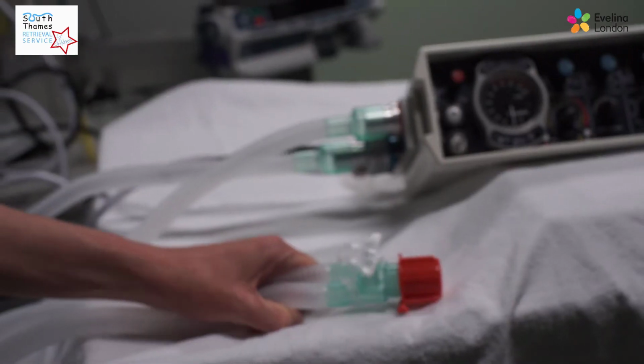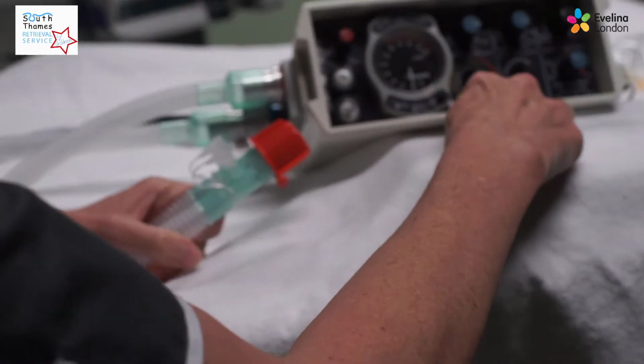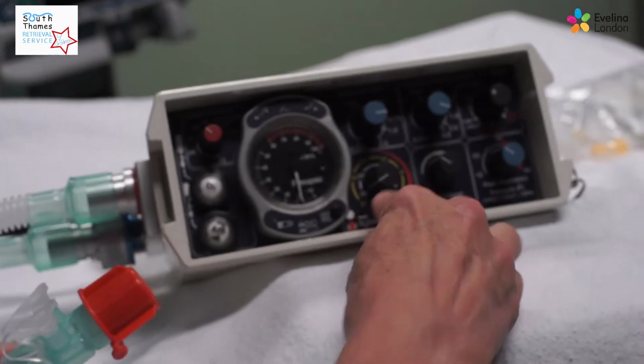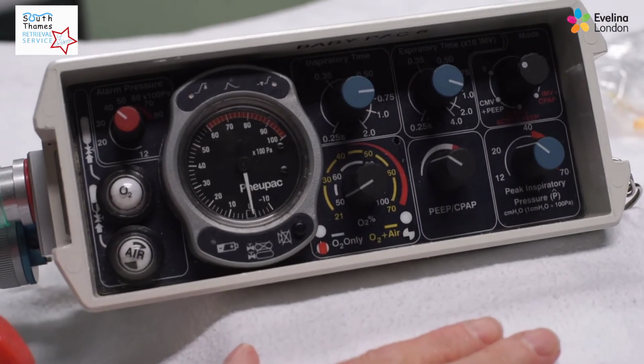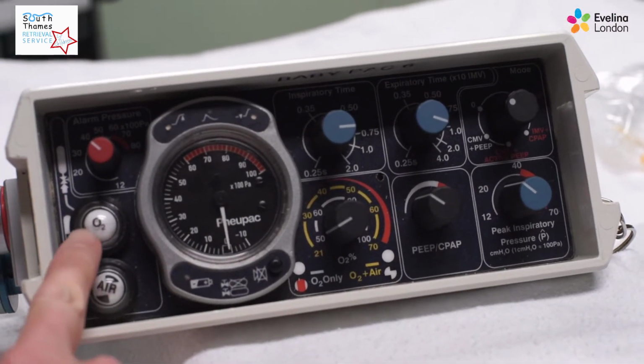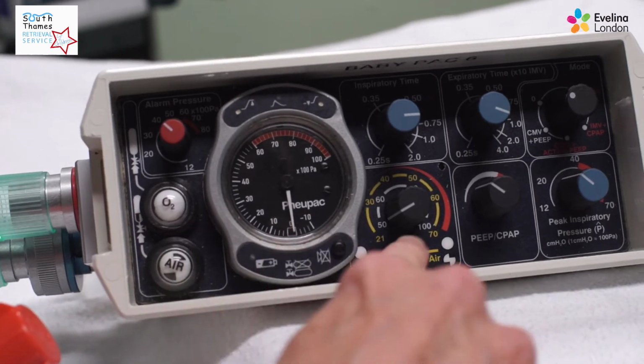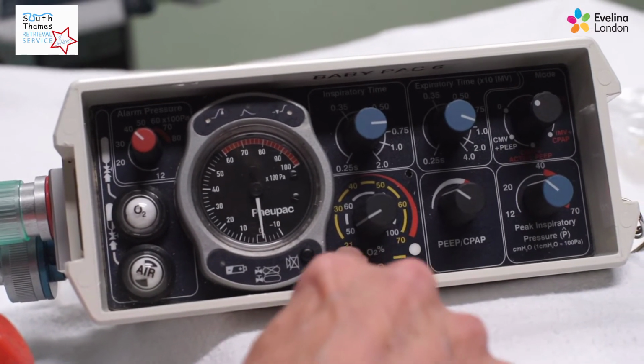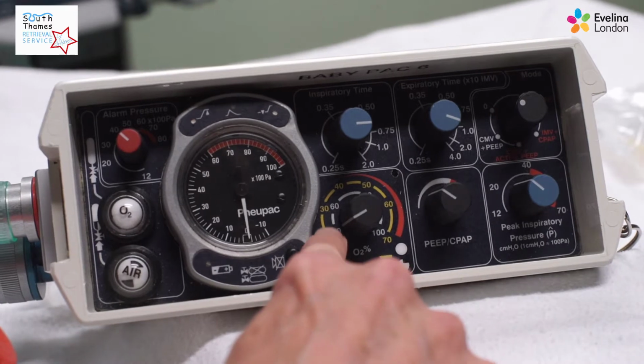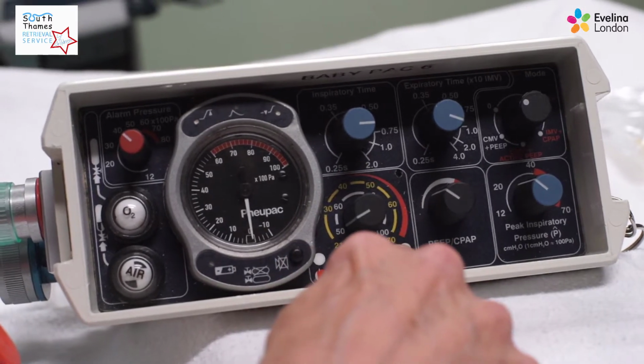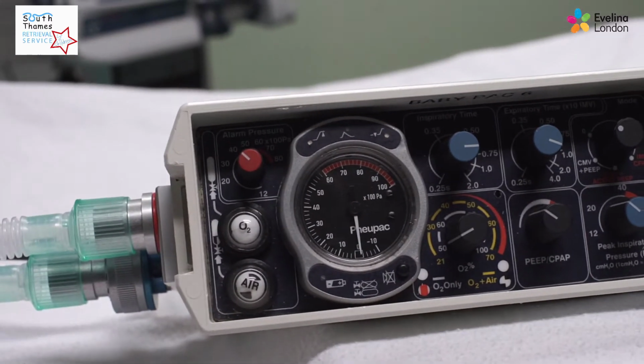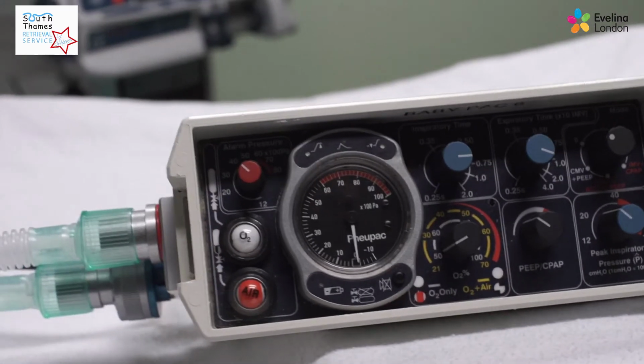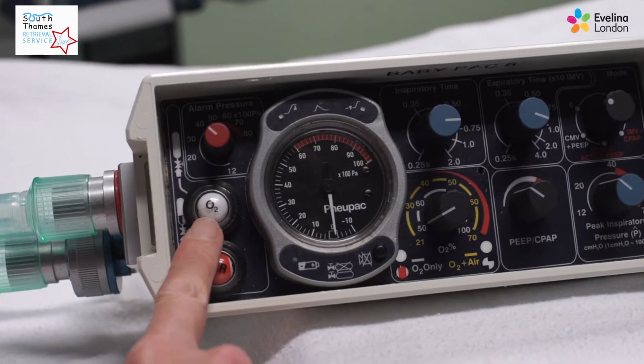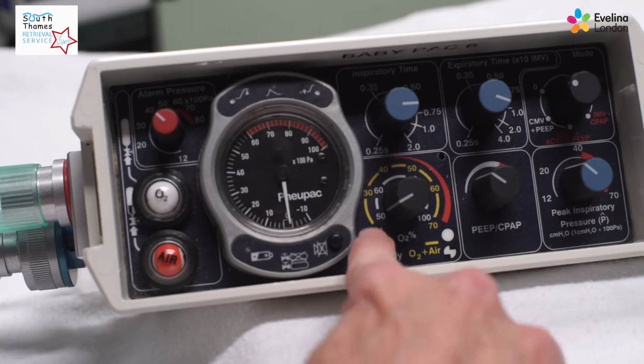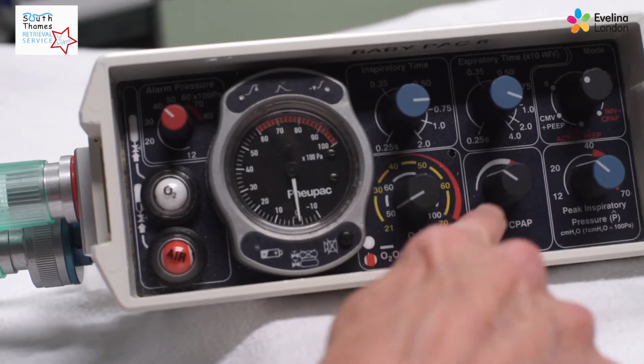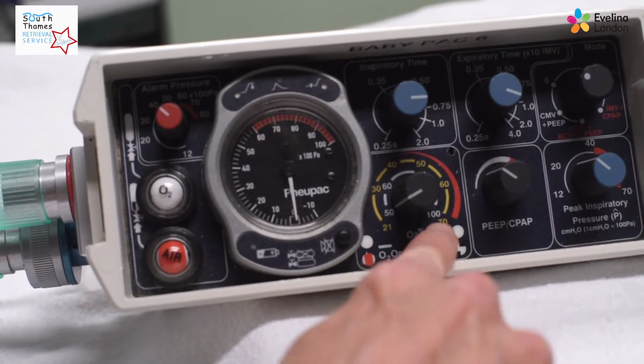Then we check the ventilator for functionality. This dial here is giving us the percentage of oxygen. Because we've got oxygen and air attached, we follow the yellow line, which goes from 21% oxygen round to 70%. If we just have oxygen attached, you follow the white line, which is 50% round to 100%.